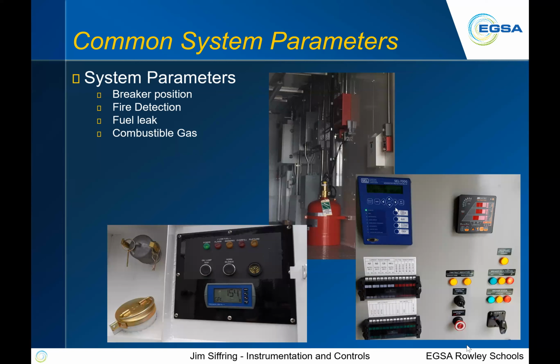First thing, breaker position. That's a key one. In my experience on the service side of the world, how often people used to get called out and the customer would say, you know, the lights are out in my building, but the generator's running. Well, did that breaker get tripped? Did the breaker get left in the open position last time maintenance was done on the genset? If we can keep track of what that breaker position is, it may save us countless headaches.